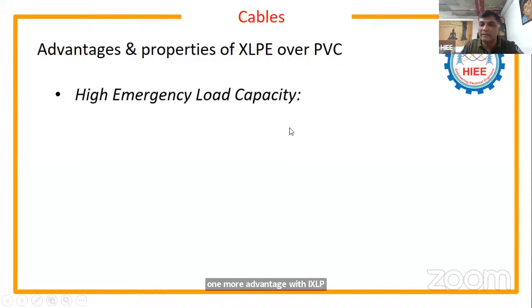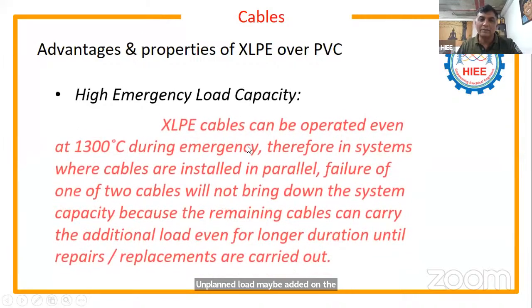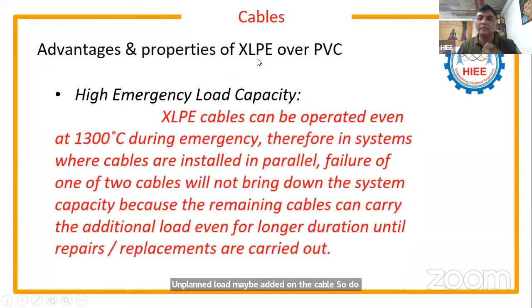And the next is emergency load capacity. Emergency load capacity in the sense, sometimes what happens, unplanned load may be added on the cable. During those times, if you go with XLPE, it can bear that extra load. XLPE can be operated even at 130 degrees, because generally in cable selection and sizing, temperature is the criteria.